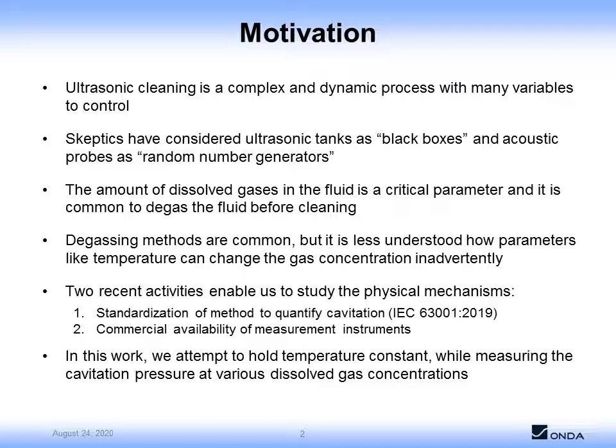There are two recent activities that enable us to take a closer look at these mechanisms. The first is the release of an international technical specification describing the method for how to quantify cavitation. And two, the availability of a measurement instrument. In this study, a cavitation meter is used to determine how cavitation changes with varying dissolved gas concentrations while keeping the temperature fixed.